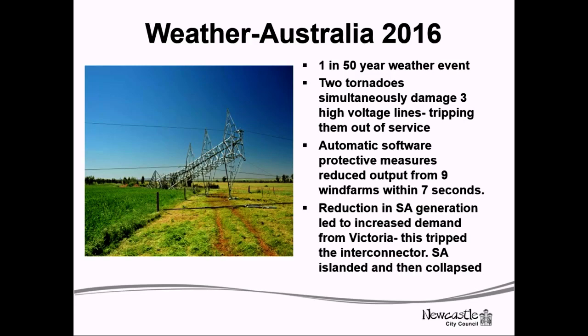The protective measures within 9 wind farms reduced their voltage to protect themselves from voltage instability, and as a result they lost quite a bit of their generating capacity. This meant that the power required by South Australia came in through the Heywood interconnector in Victoria. That couldn't take the load, so it tripped offline. Once that happened, there was no going back, and without power to power itself, the rest of the grid in South Australia tripped offline and it fell into a black grid.